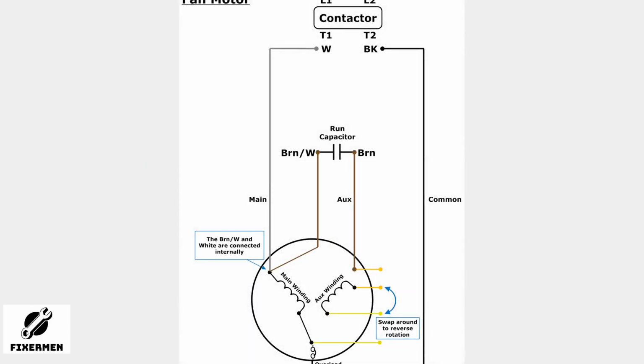Let's look at the key components in the schematic diagram. The capacitor stores electrical charge to start the fan motor. Here's what a typical capacitor looks like. Notice the cross on top. The fan motor spins the blades to circulate air. The wiring diagram shows how the motor connects to the capacitor and power supply. These components work together for efficient cooling. Now let's dive into troubleshooting.